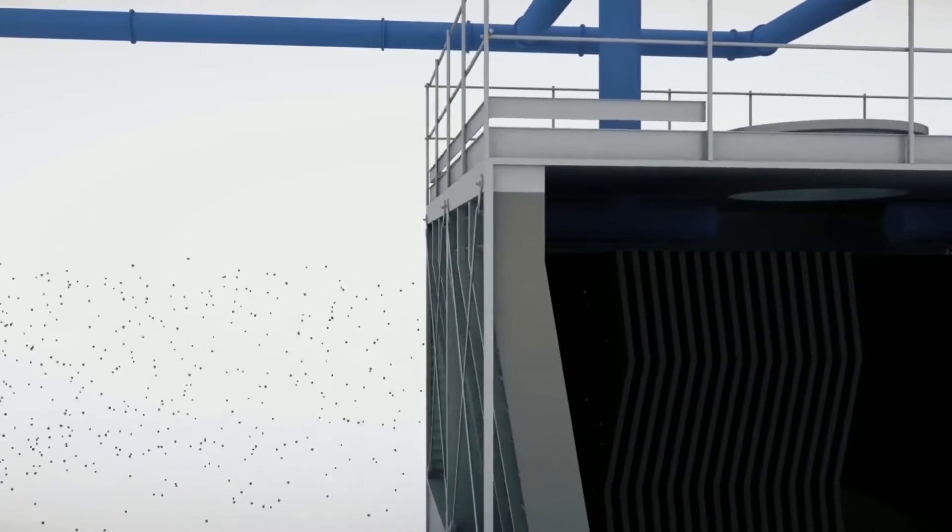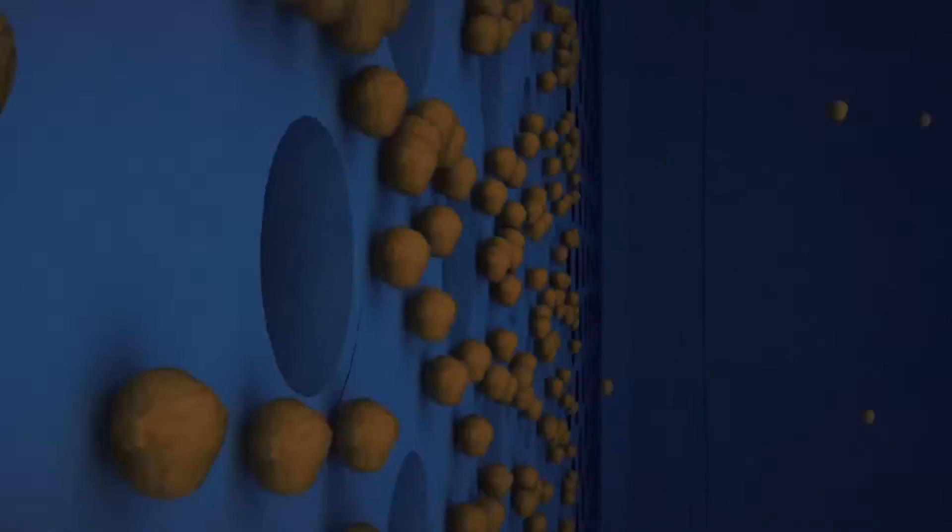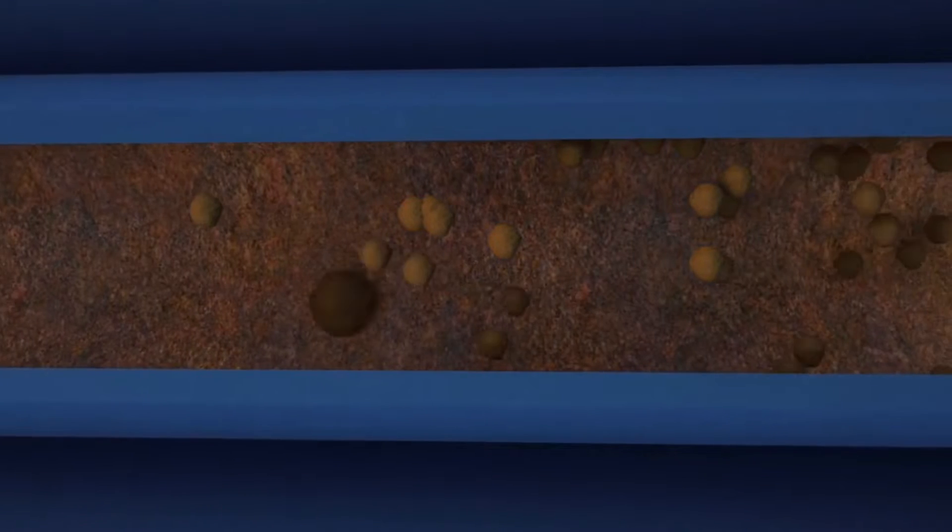Dust, dirt, and silt fouling. Cooling towers inevitably end up attracting dirt and dust from the surrounding air that settles through the system into the cooling tubes, creating an insulation layer.